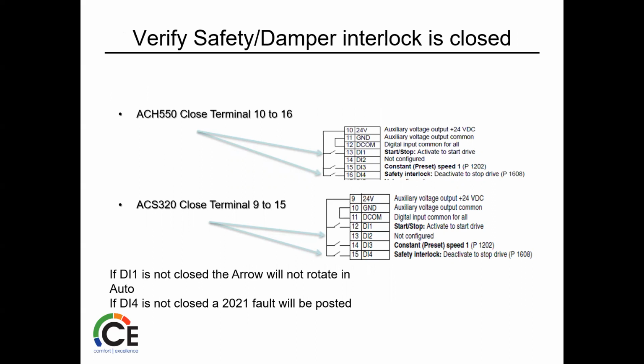So as we're talking about this, we get into parameters. That's where this DI1, DI2, DI3 comes in. It's just a part of the setting. It's going to close terminals 10 to 16. And then it's a safety interlock, deactivate the stop drive. So if DI1 is not closed, the drive will not run in auto. If DI4 is not closed, the 2021 fault will be posted, which means there's an internal safety error. So it shut itself down because there was an issue.